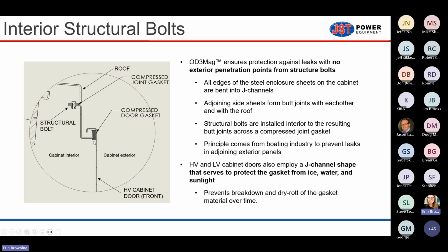I also want to point out the high voltage door is gasketed with a J channel. And so this is a side view. Where my mouse is, that's the front of the breaker. And then this J channel is the top of the high voltage cabinet door. And that is basically a shield for the gasket. So now you don't have sun beating down on the gasket. It's not completely exposed to the elements, so it withstands the test of time, and you don't have overcompression in any of the locations. So the gasket does its job really well.